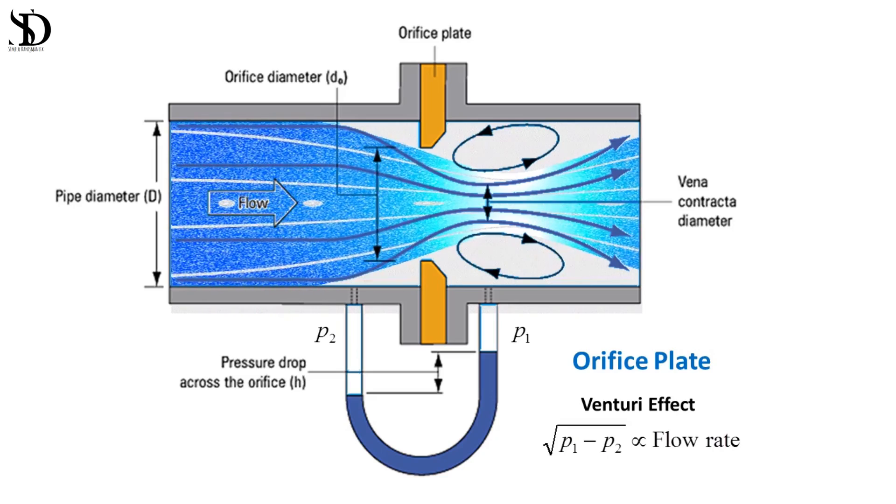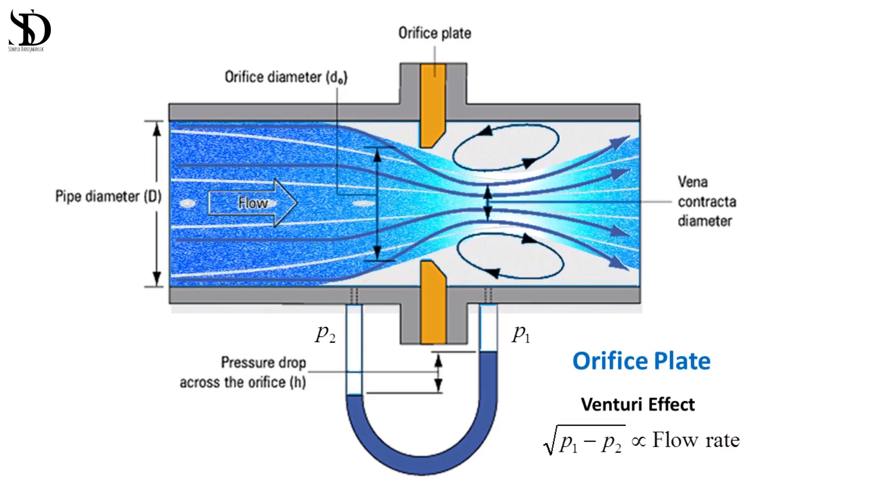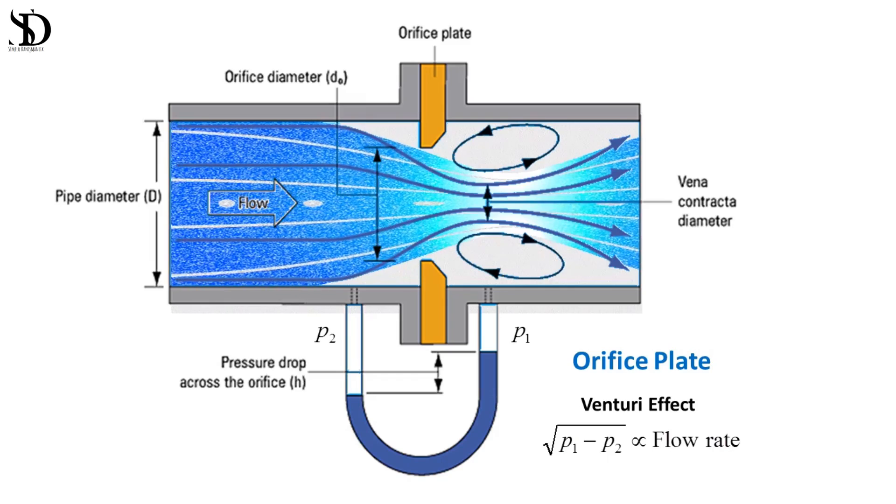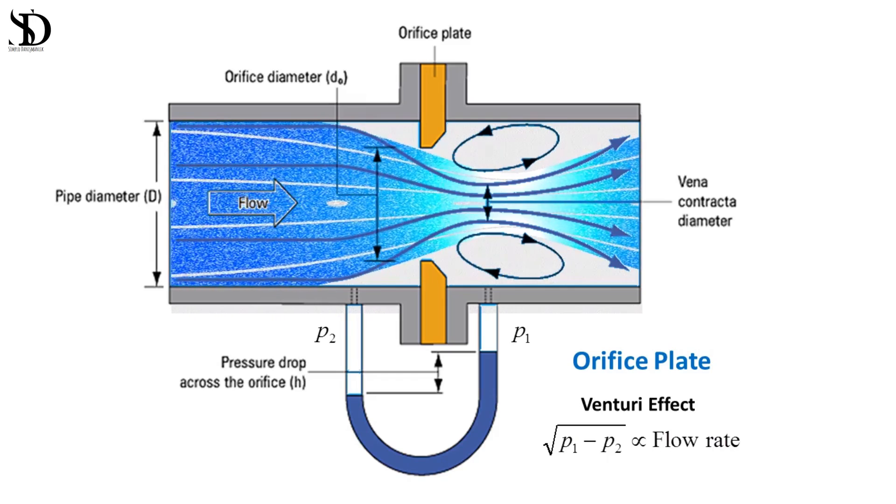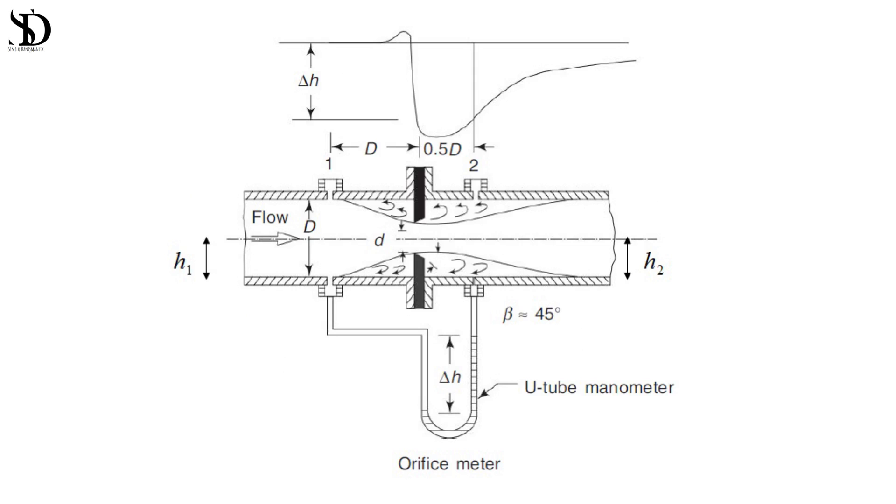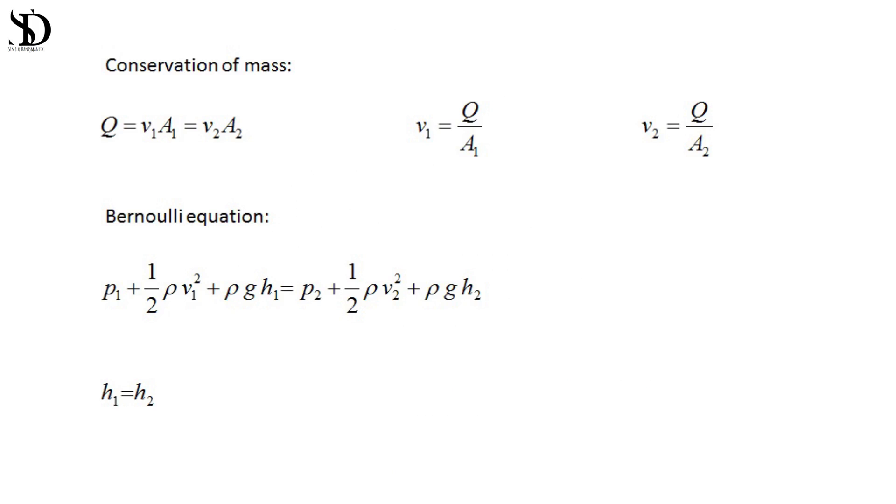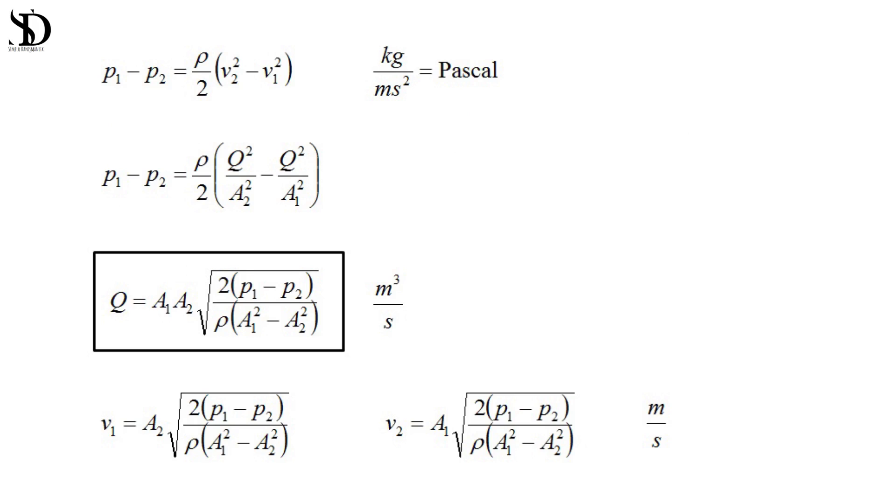As fluid passes through the orifice, it creates a pressure drop across the plate, allowing for the determination of flow rate based on the measured pressure difference. Orifice plates create a significant pressure drop and are suitable for turbulent flow conditions, however their usage might lead to energy losses. These plates come in various configurations such as concentric, eccentric, or segmented, catering to specific flow measurement needs.